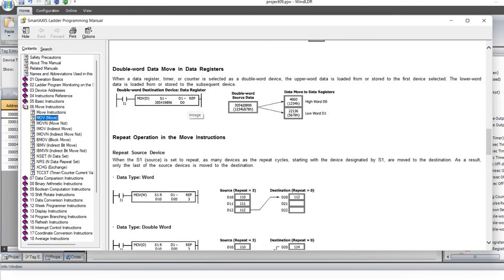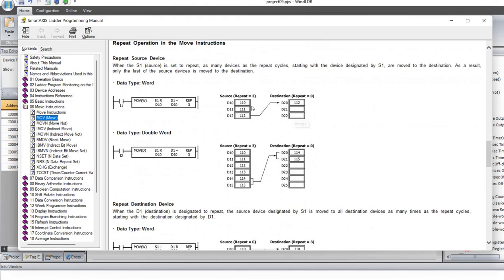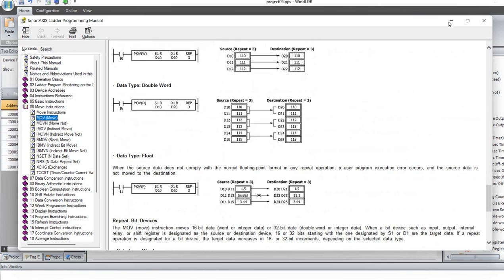If you are using double, you are using basically 16 and 16, which makes 32 bits — two registers. For example, D0 and D1, or D1 and D2, those kinds of combinations. And if you repeat this for three, you are using three registers when using a word. If you repeat three for the double word, that would be six registers — those kinds of things. I just wanted to show you the help function, because when you are programming you will need it.